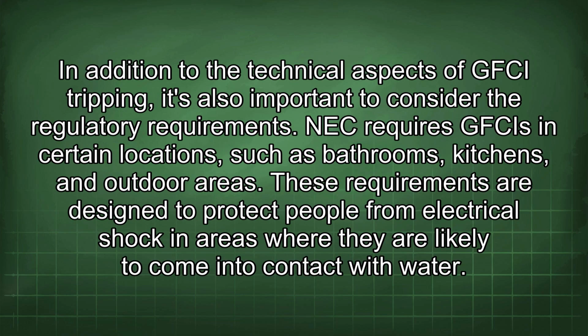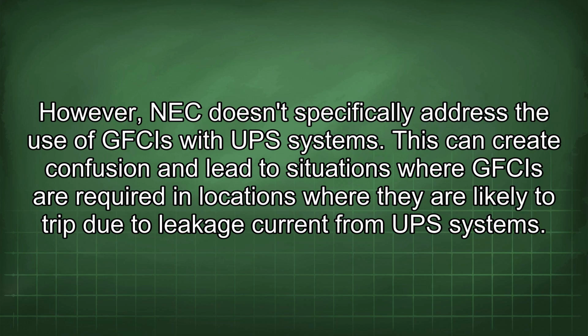In addition to the technical aspects of GFCI tripping, it's also important to consider the regulatory requirements. NEC requires GFCIs in certain locations such as bathrooms, kitchens, and outdoor areas. These requirements are designed to protect people from electrical shock in areas where they are likely to come into contact with water. However, NEC doesn't specifically address the use of GFCIs with UPS systems.